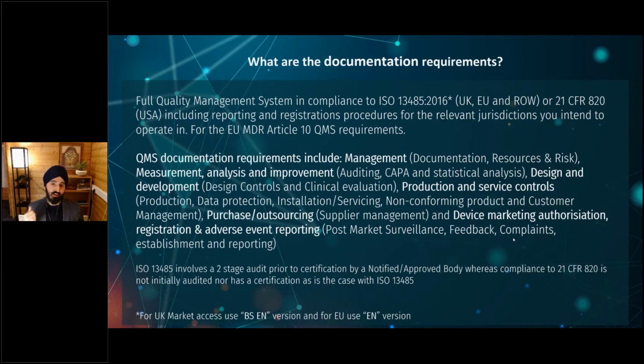For the UK, the EU, and the rest of the world, we work to a standard called ISO 13485:2016. For the UK, you want to use the BS EN version of that, and for the EU, you want to use the EN version. The difference between these two is that the BS EN has been harmonized to UK regulations, whilst the EN version has been harmonized to European regulations. And of course, in the USA, we have 21 CFR 820.